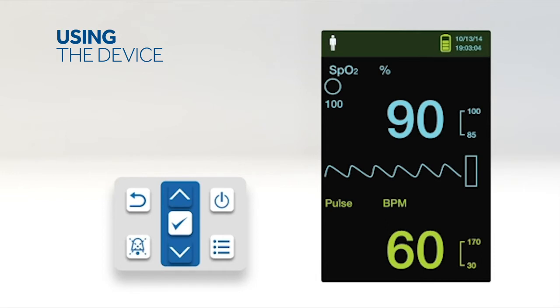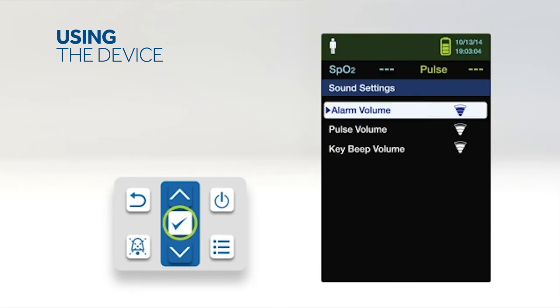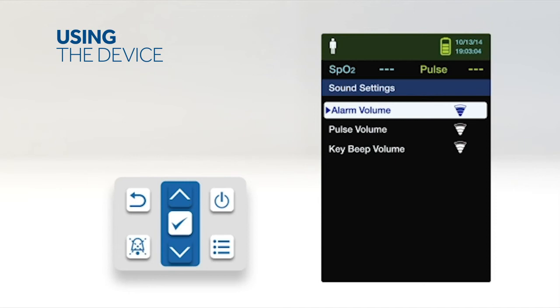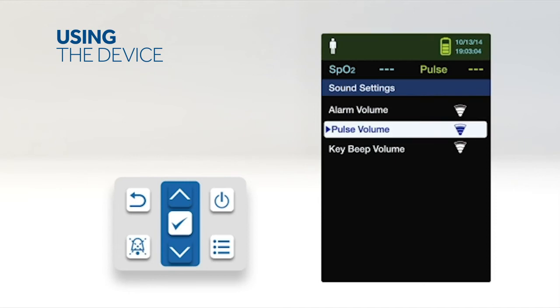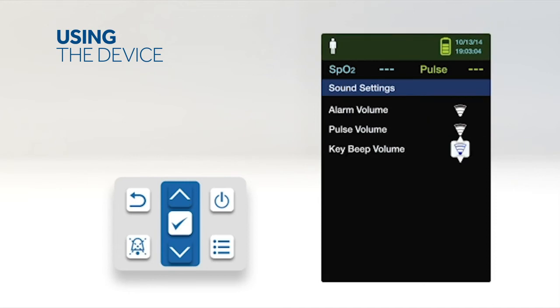To set the desired audible tone volume, select the sound settings menu. Press the OK button to select alarm volume. Press the down arrow and OK button to highlight and select pulse volume or key beep volume. Adjust to the desired volume level. Press the OK button to save the desired volume level.